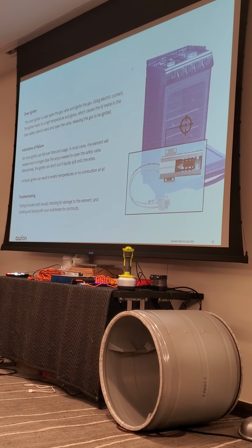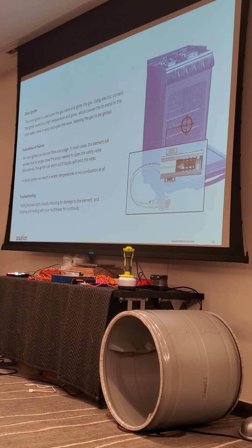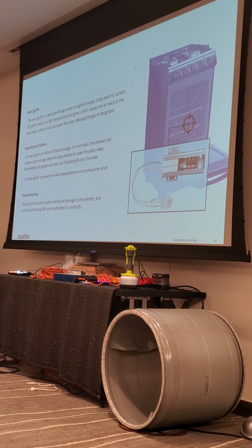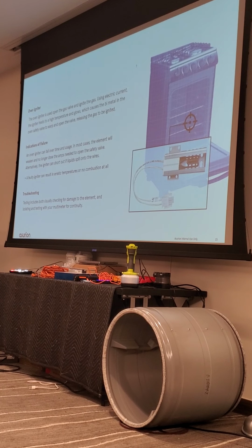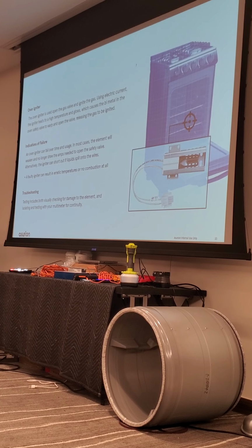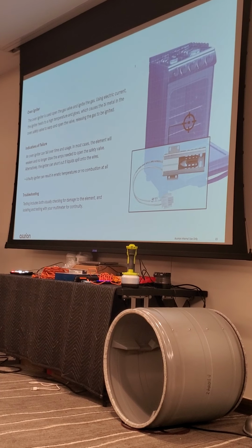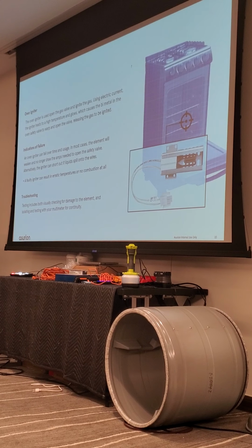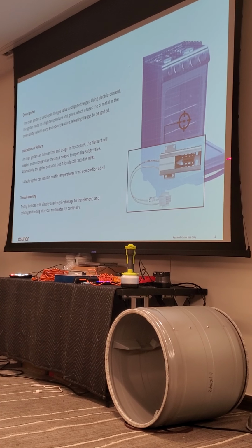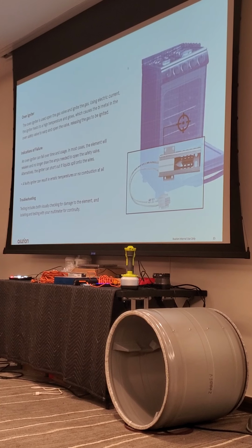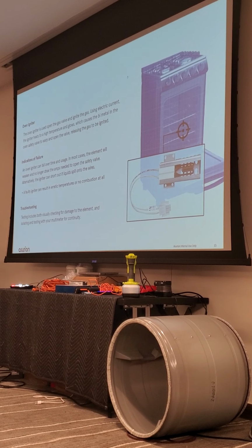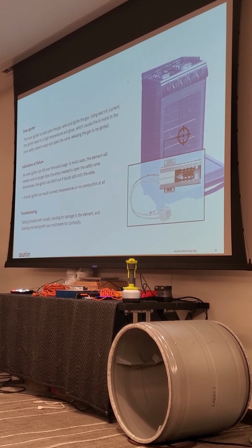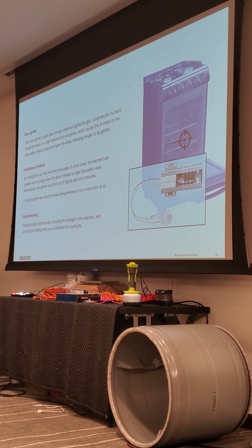So y'all need to know exactly how that works. It's very, very important how that igniter works in these, okay? You can test these for ohms, you can even test these for voltage and amperage, but amperage is the best way to test these, because about 3.3 to 3.4 is where it's going to be at full power. And then once the gas ignites, you can actually watch the amperage drop down, okay?